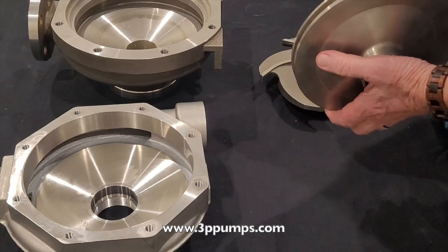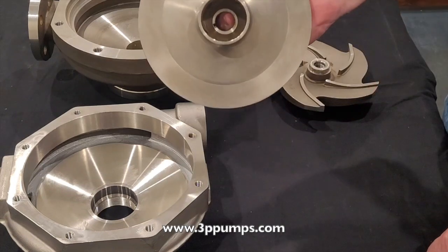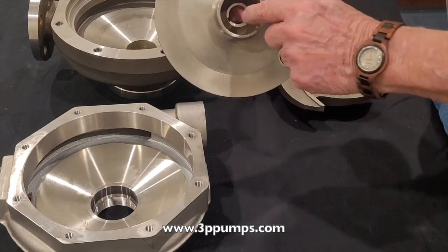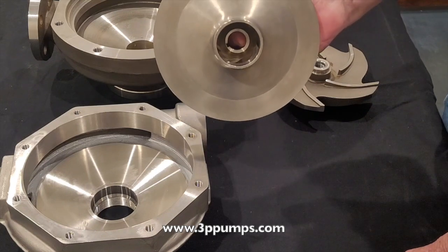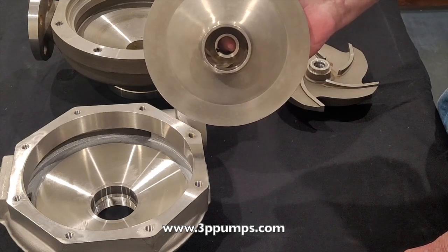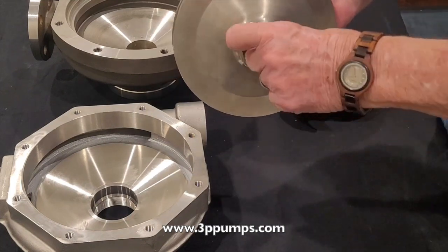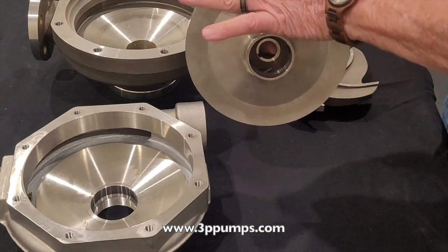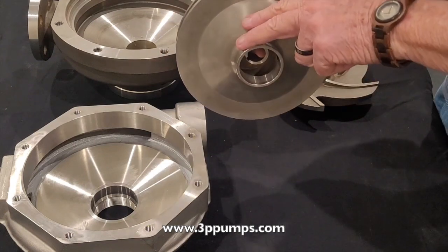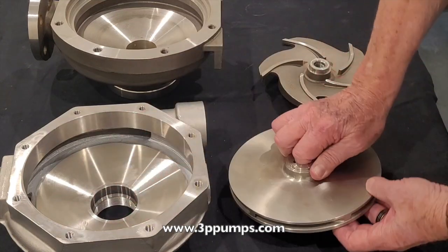Now, we were talking about the liquid at the eye of the impeller, and this is your eye of the impeller. When that goes in there, right there, that liquid changes to gas if the pressure is not high enough, okay? So on this type of impeller, that's where it happens, right there. And the high pressure is trying to escape back to suction, and it's going right here, but it's being stopped by this close tolerance right here, okay?